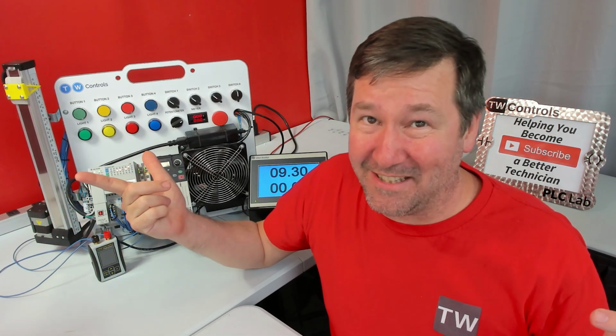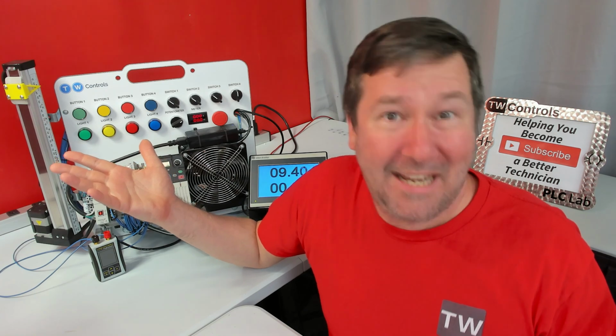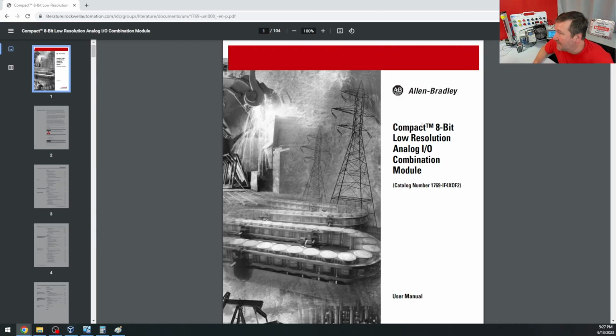8-bit? Now, I know what you're thinking. Well, who in the world would buy an 8-bit module? Tim did. This looks like the perfect module when you need to read one level and control a pump speed. So we have a 1769 IF4X OF2. This is a CompactLogix module. But notice right here, it says compact 8-bit low resolution analog I/O combination module.